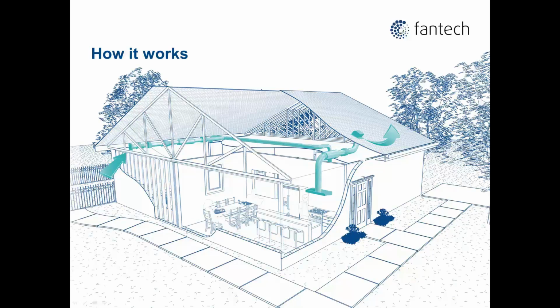Once the system is commissioned, it works like this. As the exhaust fan is turned on, a current transducer sensor on the exhaust fan's power wiring activates the make-up air control. The make-up air control then opens a 24-volt damper and commands the make-up air fan to deliver air to the home. The make-up air fan's speed is automatically varied as necessary via a 0 to 10 volt DC signal to compensate the exhaust airflow rate within its range from minimum to full speed operation and any rate in between. If fitted, the optional heater will be enabled to automatically add variable heat to the air to the pre-programmed discharge temperature set point. Sufficiently tempered air can now be delivered directly to the space where the exhaust fan is pulling from.